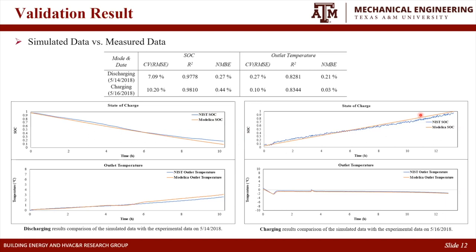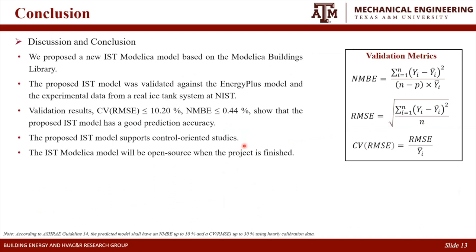As you can see in these figures, the numerical model reflects the system dynamics compared with the real ice storage tank (IST) test bed. Based on our previous slides, we concluded that the new ice storage tank (IST) model is proposed and the proposed model was validated against a real ice storage tank (IST). The results of CVRMSE and NMBE show the model has good prediction accuracy. And most importantly, the proposed model supports control-oriented studies. We plan to open source this model when our project is finished.